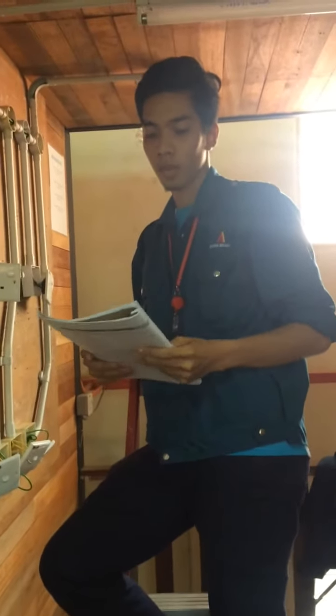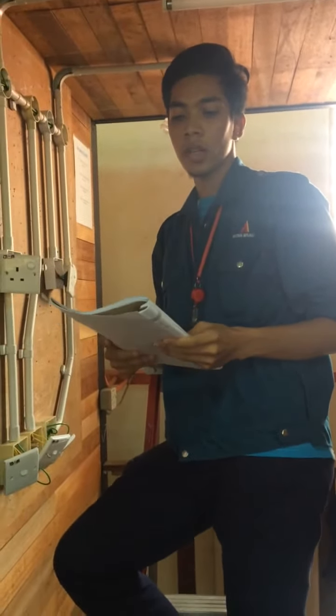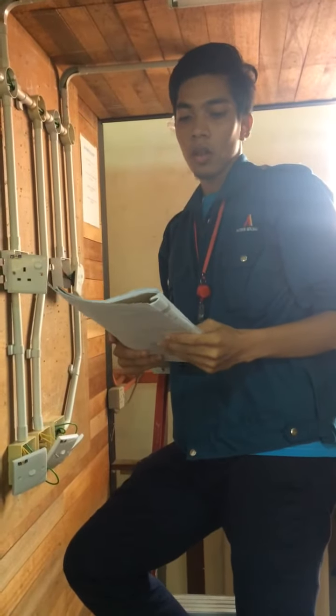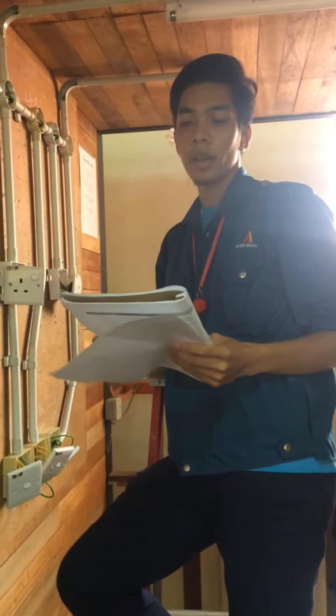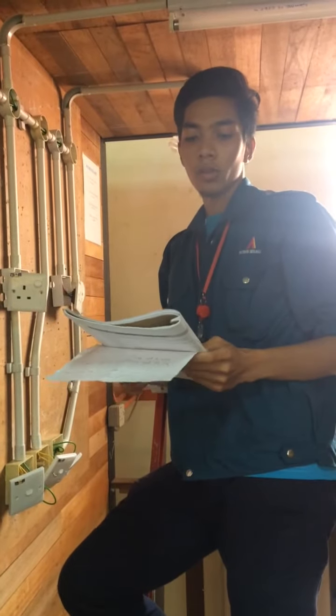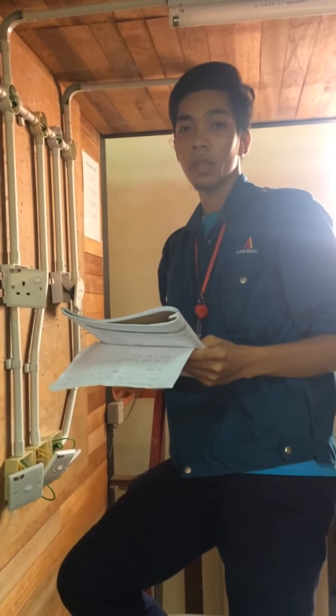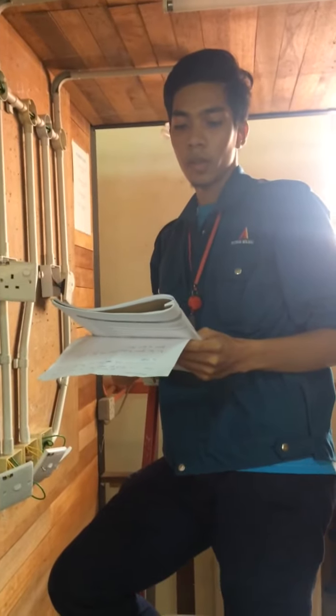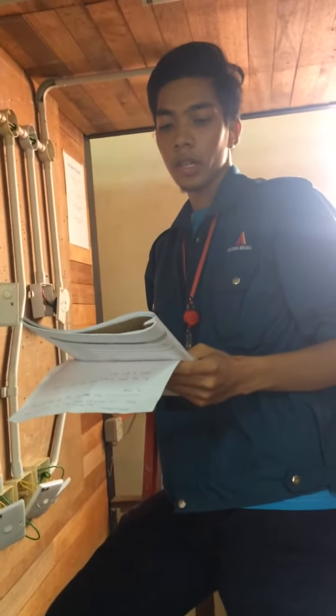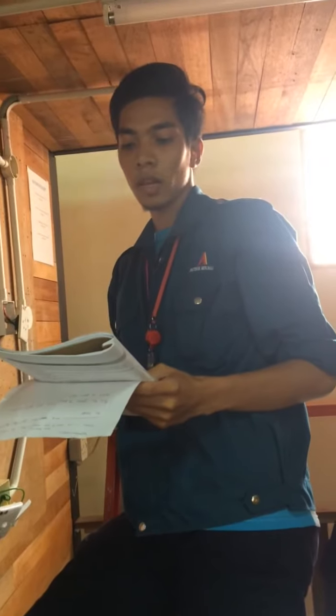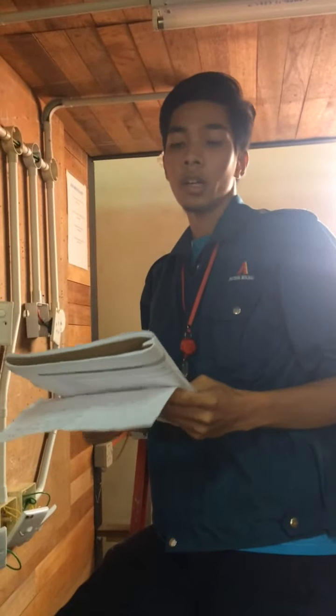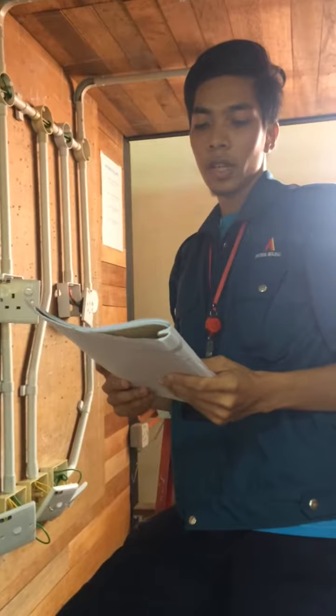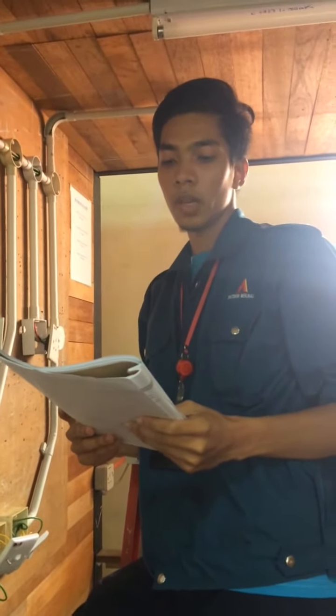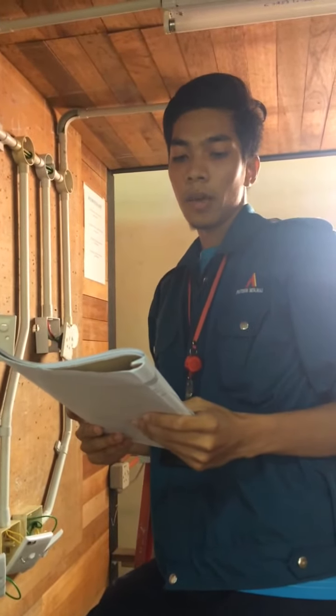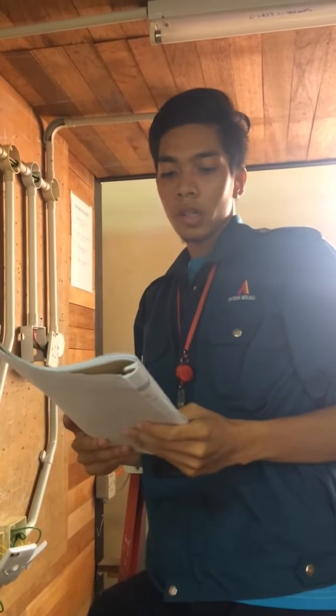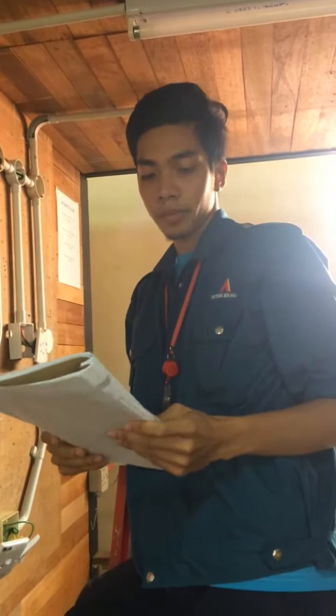Today I will show and teach you how to make a polarity test and show you the tutorial step by step. First, I will read the equipment and procedure. The equipment is a multimeter and the wiring trainer. The procedure: first, select the range of the multimeter to ohm. Place the probe as shown in figure 3.1 and create the temporary connection between the earth terminal and the live terminal at the switch point. Record the reading. Repeat the step, changing the temporary connection between earth terminal and live terminal at the lamp point. Switch on the switch and record the reading.